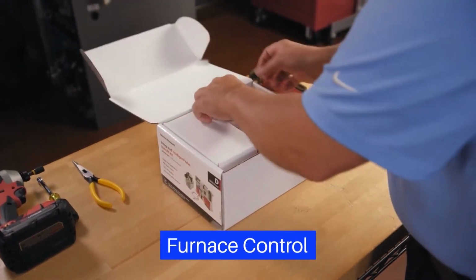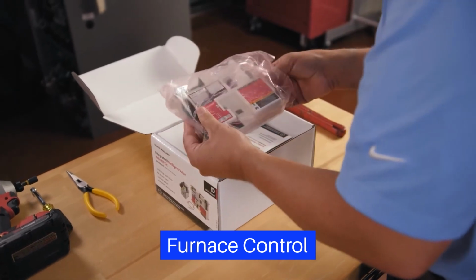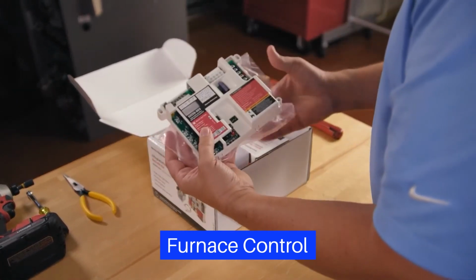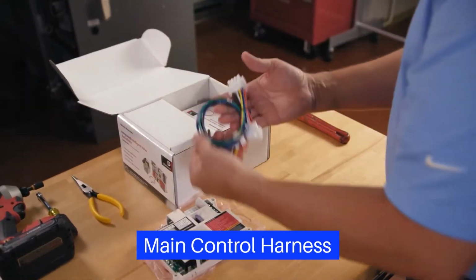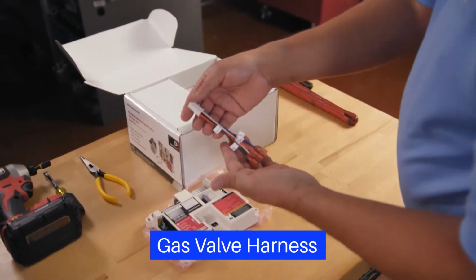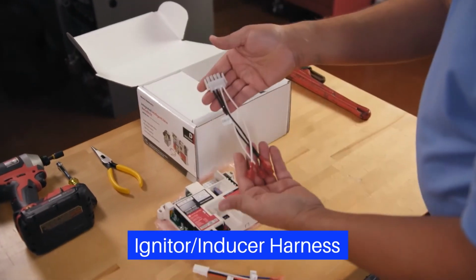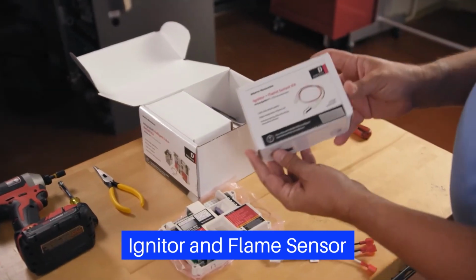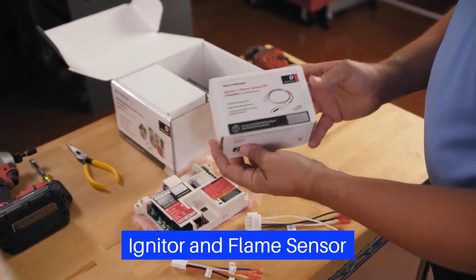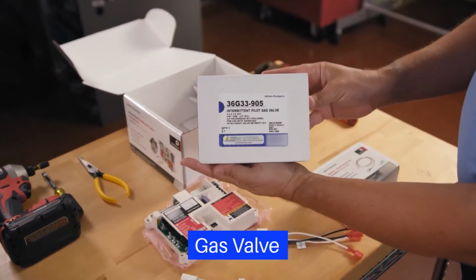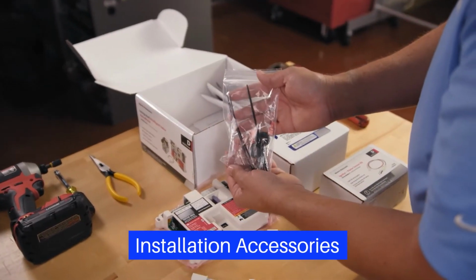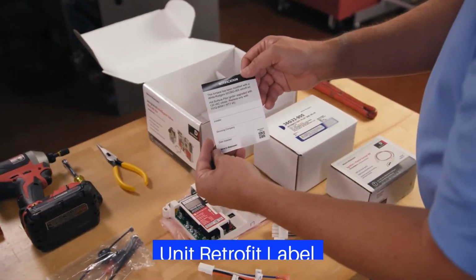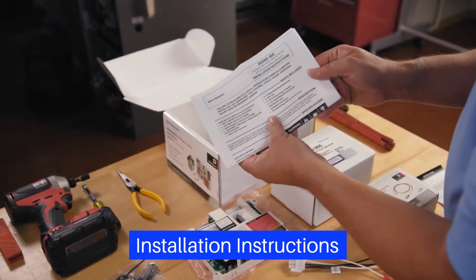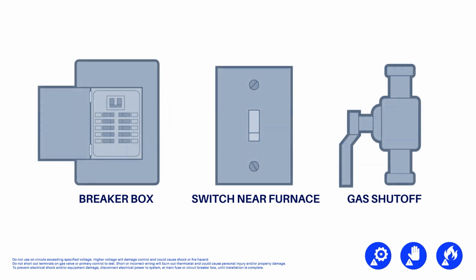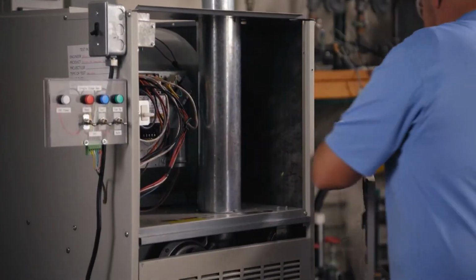The box includes a 50I56D-905 furnace control board with a troubleshooting label on the control cover, main control harness, gas valve harness, igniter inducer harness, 120-volt igniter plus flame sensor kit for pilot assembly, intermittent pilot gas valve, installation accessories, unit retrofit label, and step-by-step instructions for easy installation. First, ensure power and gas are disconnected prior to servicing the unit. Remove the access panel.